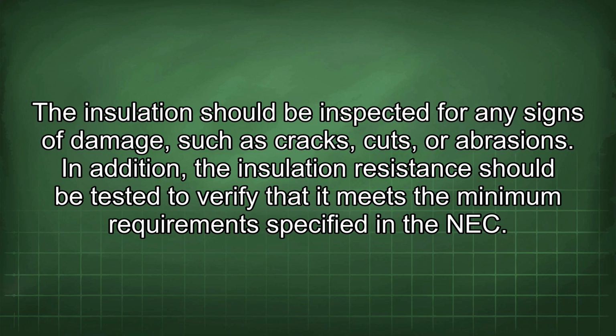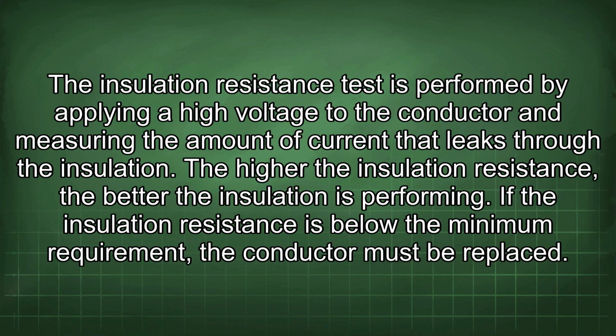In addition, the insulation resistance should be tested to verify that it meets the minimum requirements specified in the NEC. The insulation resistance test is performed by applying a high voltage to the conductor and measuring the amount of current that leaks through the insulation. The higher the insulation resistance, the better the insulation is performing. If the insulation resistance is below the minimum requirement, the conductor must be replaced.